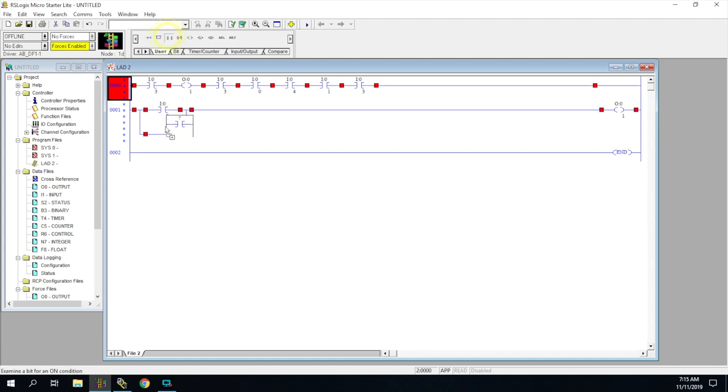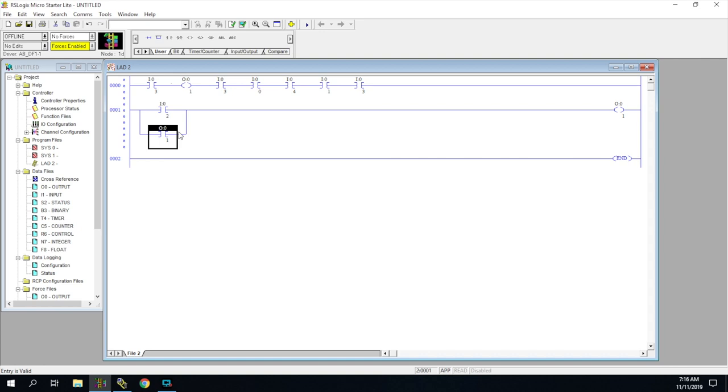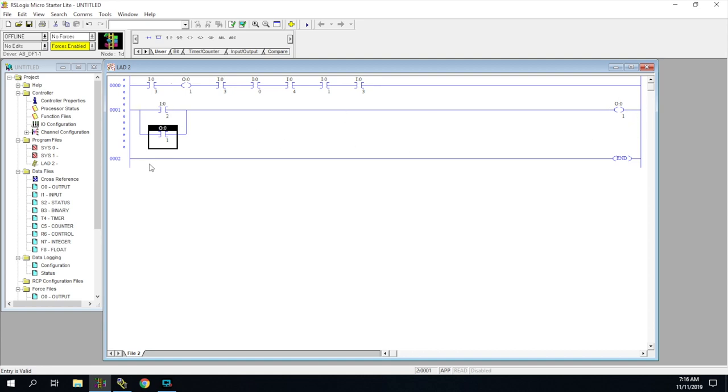So we're going to grab a new instruction. I'm just going to go ahead and put it over here, and I can go over and hover over my output. And it's actually going to take that address, and we're going to use that address as an input. So yes, output addresses can be used as inputs, but they must be connected to an output that is going to be energized. Because there's a bit in there that's going to be a 1 or 0. And so we can take that bit, and we're going to flip it on with one thing, and then we can flip it off or use it somewhere else in the program. So now if I was to press this I colon 0 slash 2, it would energize my output, and then it would actually latch this instruction right here.